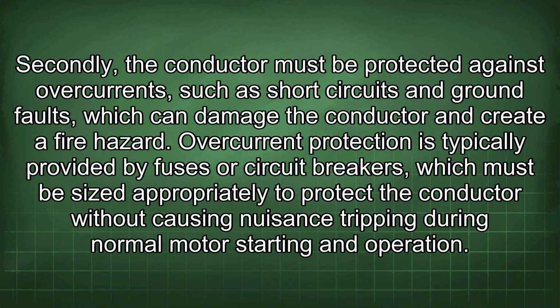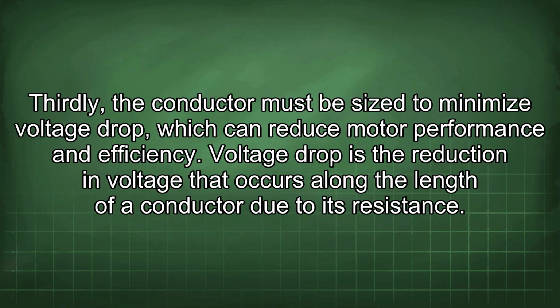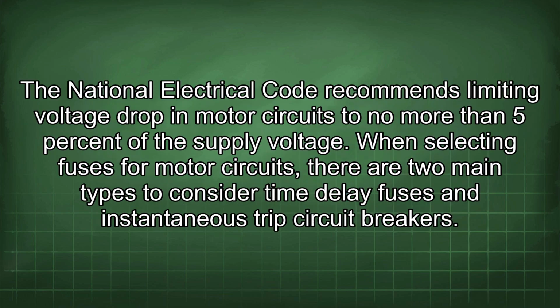Overcurrent protection is typically provided by fuses or circuit breakers, which must be sized appropriately to protect the conductor without causing nuisance tripping during normal motor starting and operation. Thirdly, the conductor must be sized to minimize voltage drop, which can reduce motor performance and efficiency. Voltage drop is the reduction in voltage that occurs along the length of a conductor due to its resistance. The National Electrical Code recommends limiting voltage drop in motor circuits to no more than 5% of the supply voltage.